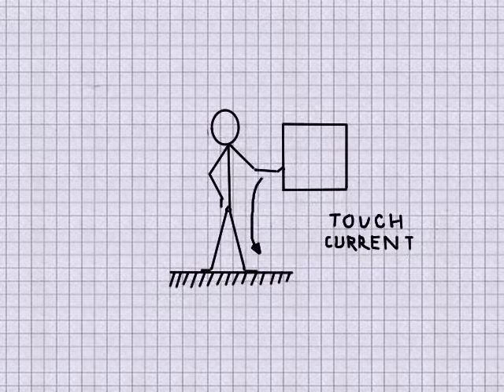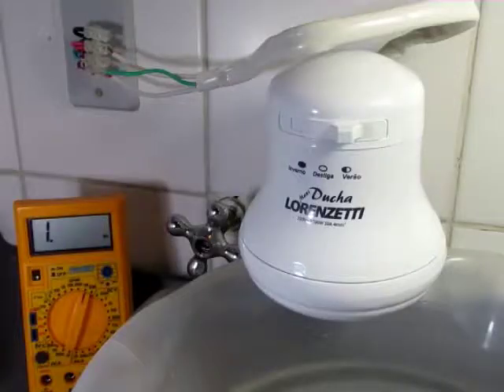We also tend to think, at least I do, that any modern electric or electronic product should not make a human body conduct any current at all. 0 amps. Again, the IEC experts define what they call the touch current, which is electric current through a human body when it touches one or more accessible parts. In some cases a 3.5 mA current or more is admissible by their standards. I have got the impression that the Maxi Ducha seems to comply with all those standards. No device can guarantee safety by itself, and safe practices should go along, like proper installation, maintenance and operation.